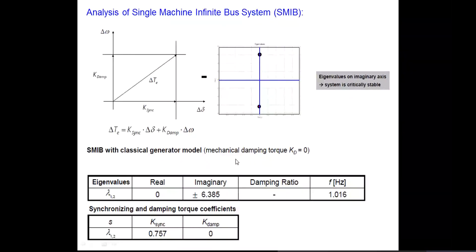For a simple system, the electromagnetic torque is represented as the sum of two components: one is the synchronizing torque component, which is a function of delta, and the other is the damping torque component, which is a function of omega. On the delta-omega axes, the vector K_damp times delta-omega represents the damping torque, and the synchronizing torque coefficient times delta represents the synchronizing torque. The electromagnetic torque del_Te is the phasor sum of these two components.